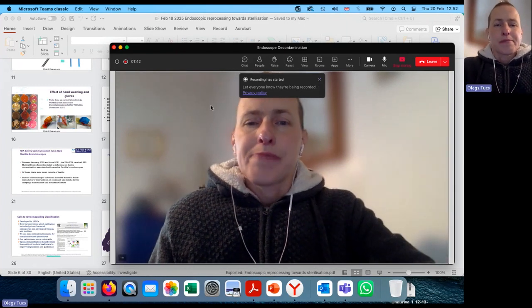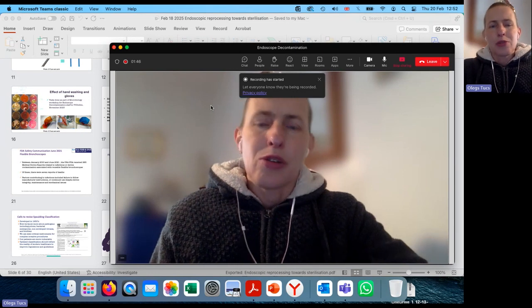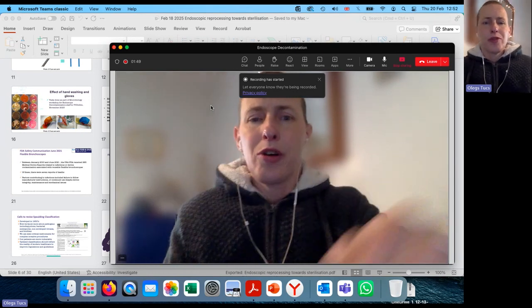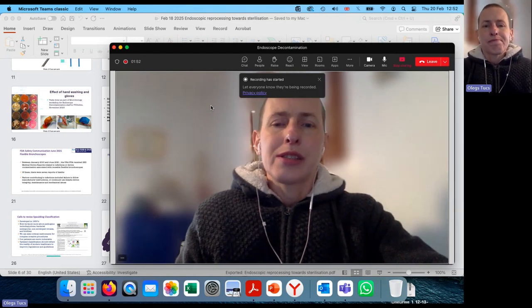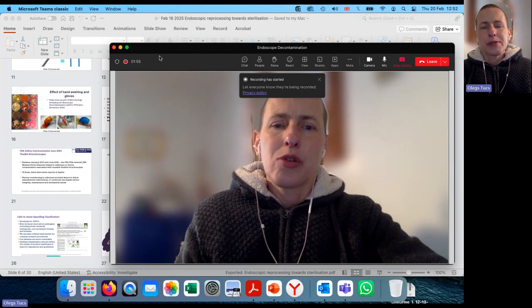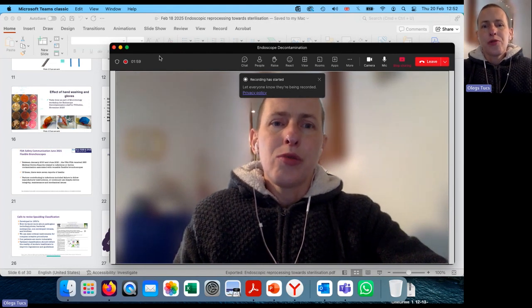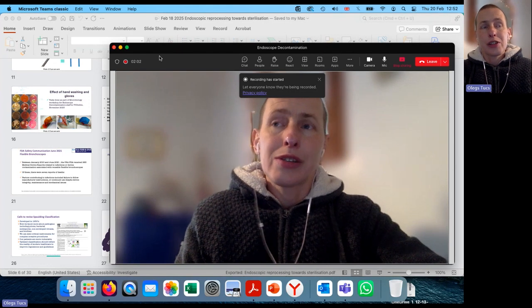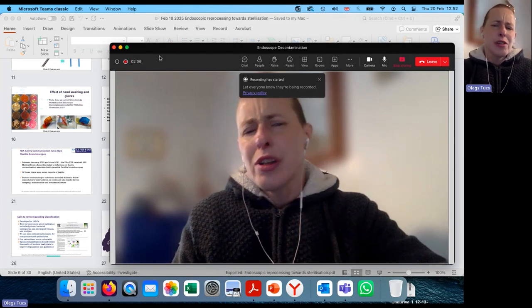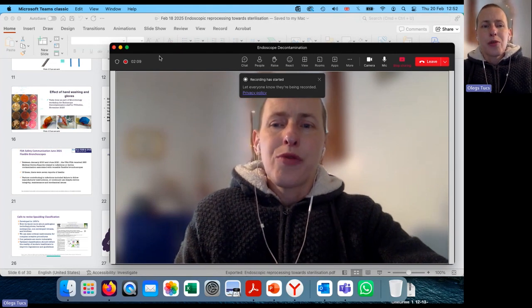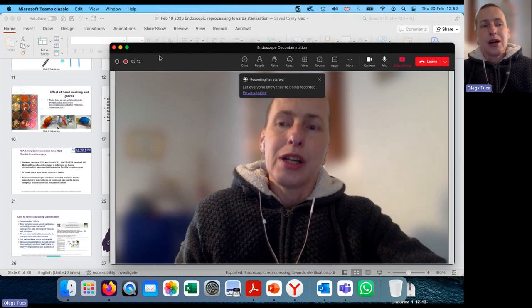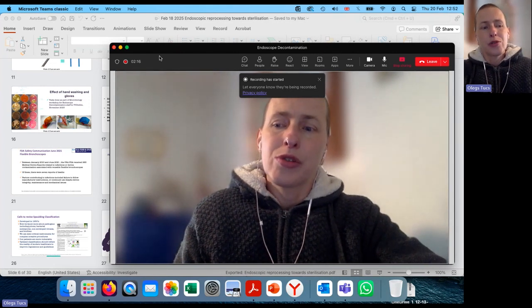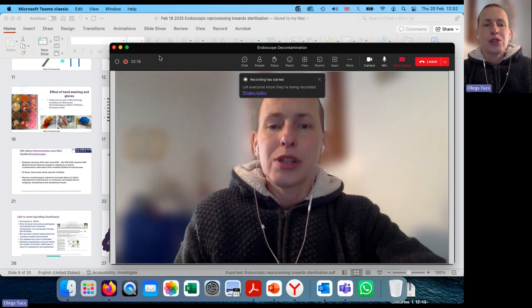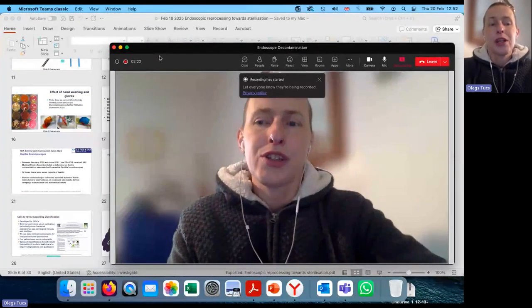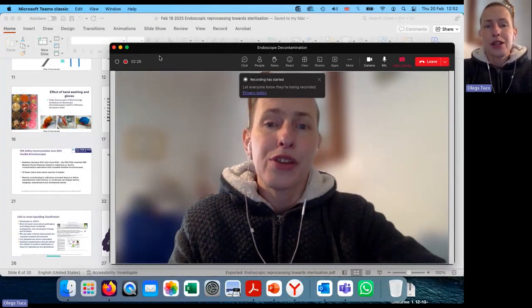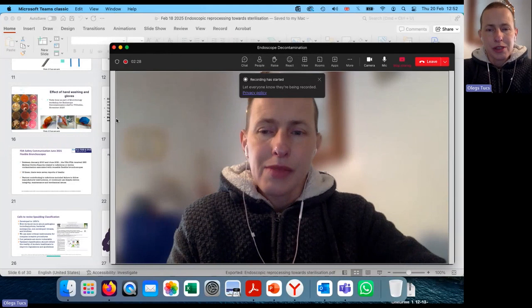I suppose in both ultrasound probes and endoscopes, as I happen to talk to you about both those things, there is one tendency. In ultrasound probes, a tendency to slowly but surely move from low-level disinfection to high-level disinfection. In endoscopes, the tendency is to slowly but surely move from high-level disinfection eventually to sterilization, either sterilization of reusable scopes or use of single-use scopes which are already delivered sterile. But high-level disinfection is still the major method of reprocessing flexible endoscopes.